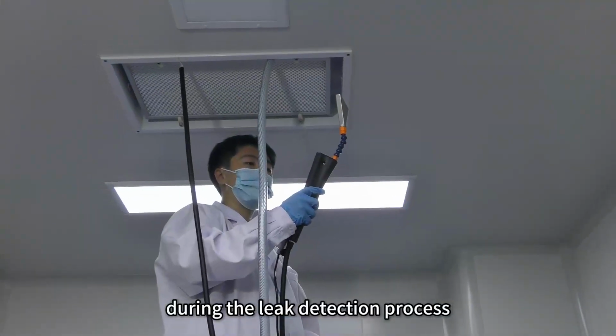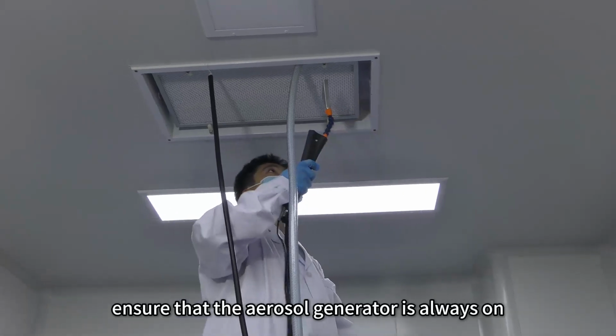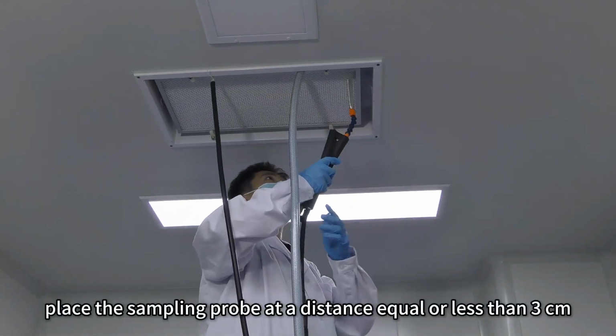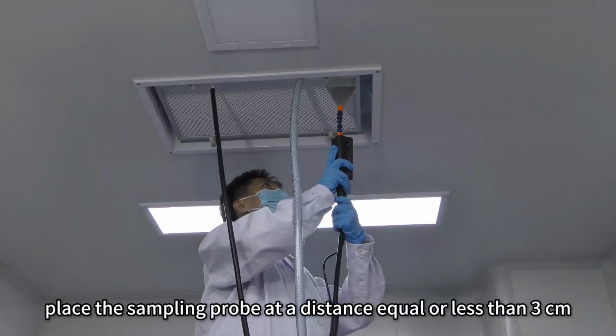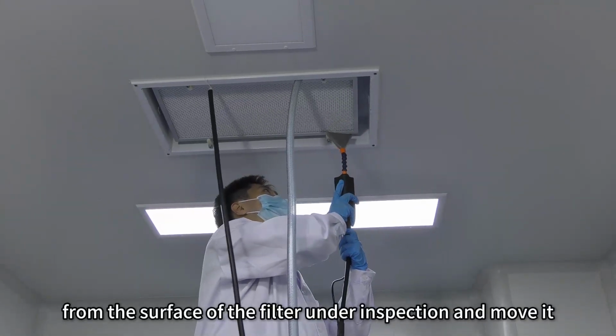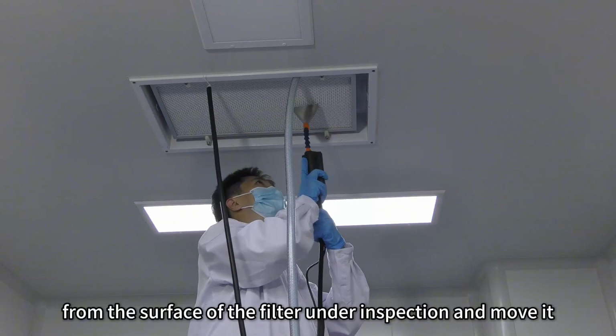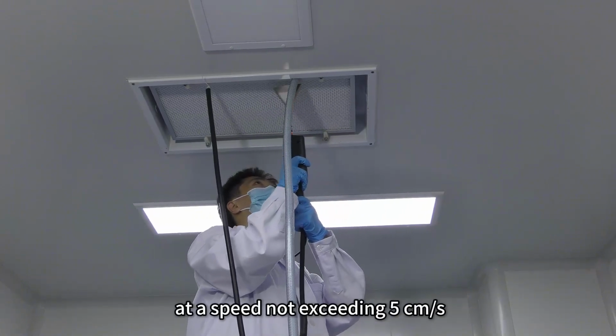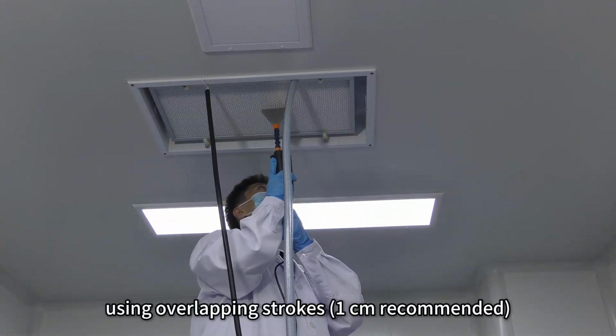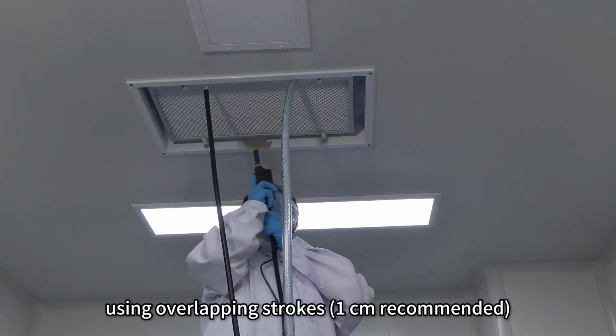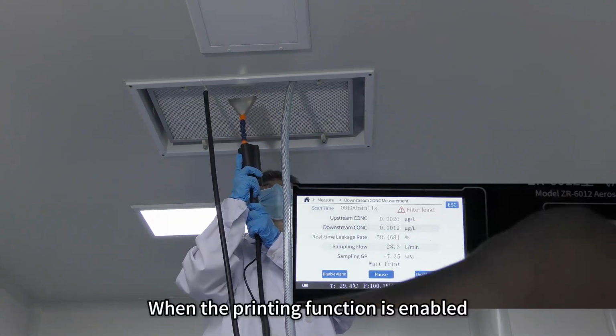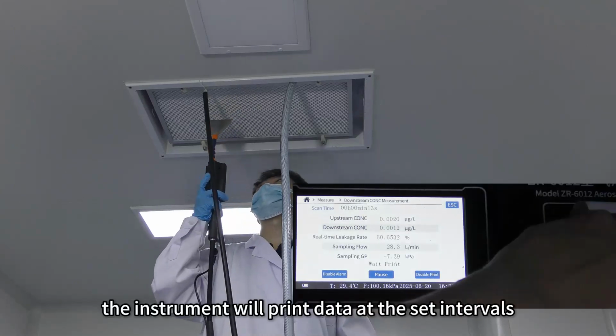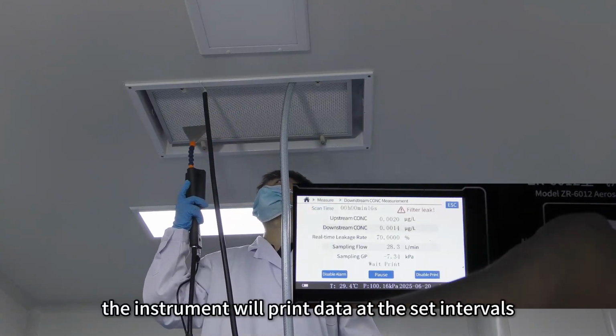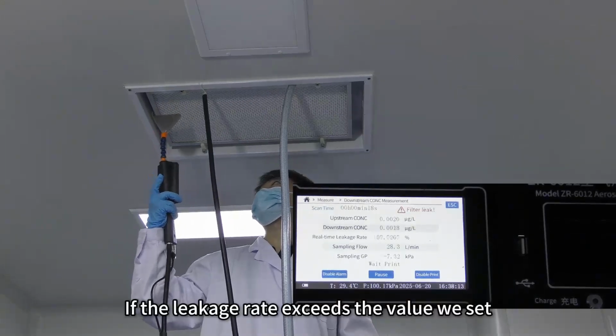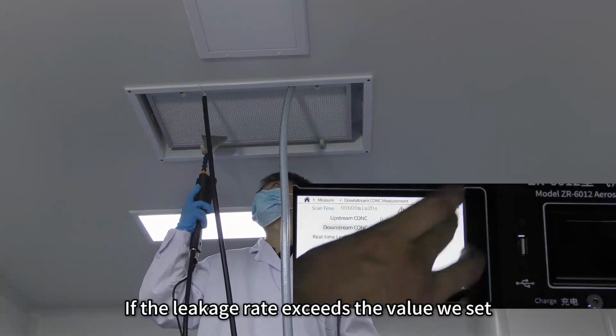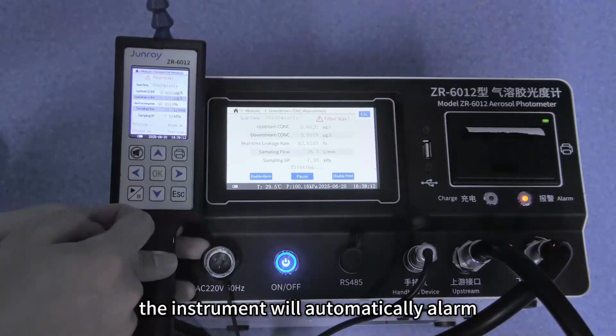During the leak detection process, ensure that the aerosol generator is always on. Place the sampling probe at a distance equal to or less than 3 cm from the surface of the filter under inspection and move it at a speed not exceeding 5 cm per second. Using overlapping strokes, 1 cm is recommended. When the printing function is enabled, the instrument will print data at the set intervals. Open the alarm. If the leakage rate exceeds the value we set, the instrument will automatically alarm.